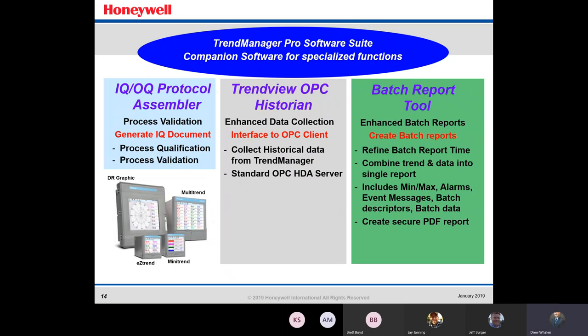For companion software of the Trend Manager Pro suite, you have the IQ/OQ Protocol Assembler for process validation — you can generate IQ documents, process validation, and process qualification. Next is the Trendview OPC Historian for collecting and storing historical data from Trend Manager. And we have the Batch Report Tool for enhanced batch reports — you can create secure PDF reports including min and max alarms, event messages, batch descriptors, and batch data, combining trend and data into a single report. Very useful if you're running batches all day.